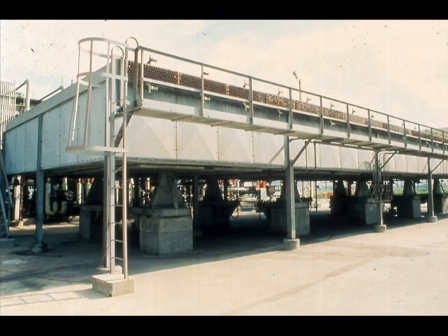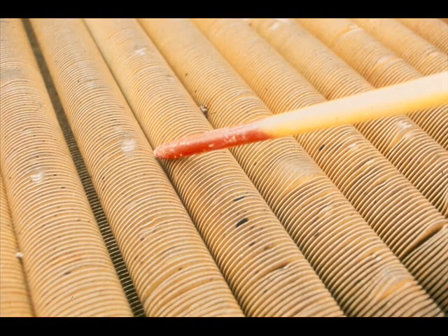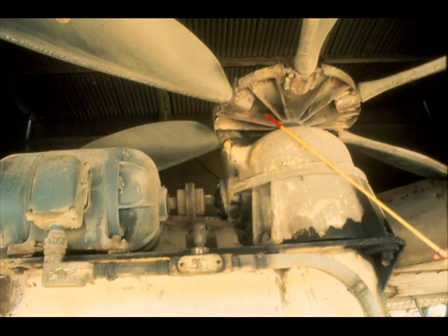The second basic application of a cooling fan is seen here on this air fin cooler. This apparatus is practically identical in operation to a radiator on your automobile. The liquid to be cooled is pumped through tubes being pointed out here. Metal fins connect to the tubes, dissipating the heat from the metal tubes. In turn, the fins are cooled by the air blown across them by the cooling fan, being pointed out.